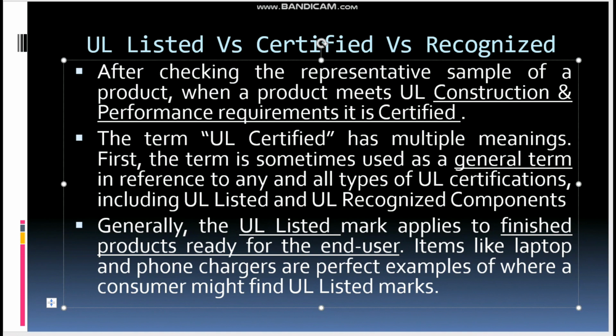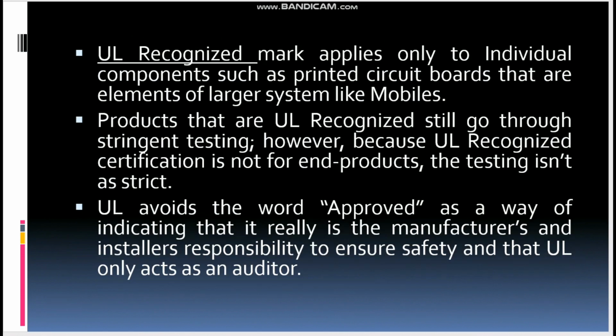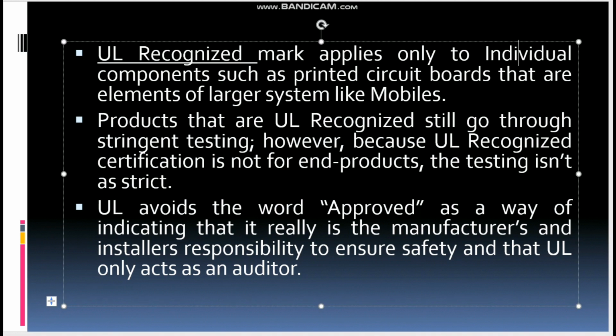For example, we just saw the butterfly valve, and that is a finished product. If I get the butterfly valve, I can quickly install it, so it is ready for use. But a butterfly valve has lots of internal components, like a nut, bolt, and different items. I don't need to care about these individual items, because I am talking about the final product, that is the UL listed one. Coming to UL recognized, this mark applies only to individual components.